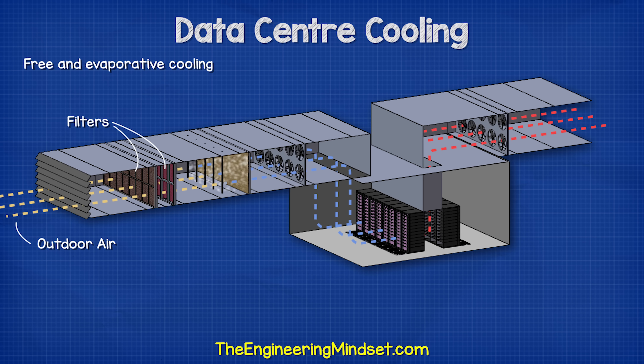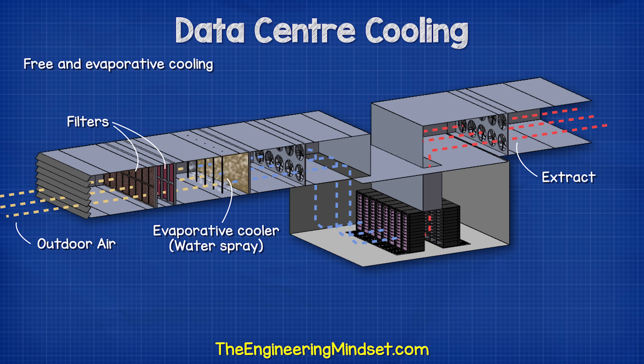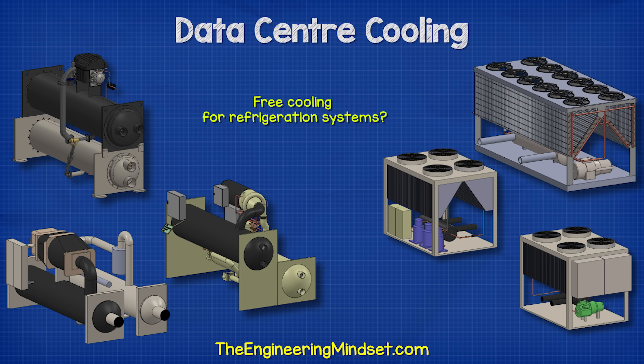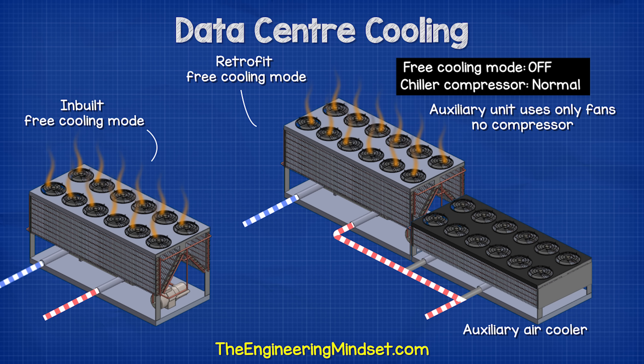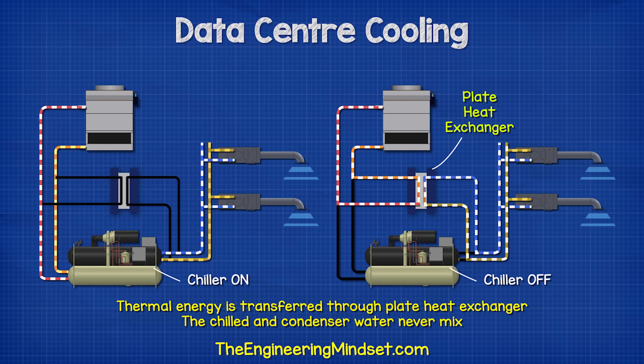Newer data centers built in cooler climates do not use refrigerants — they instead use free and evaporative cooling. In this design, outdoor air is sucked in through some filters, evaporative coolers spray water into the airstream to cool and humidify it, and the air flows directly into the server room with the hot exhaust air being separated and extracted back out to the atmosphere. Data centers with refrigeration systems can also make use of free cooling when the outdoor air is cool enough. For example, an auxiliary air-cooled condenser can be fitted which uses fans to remove as much thermal energy as possible from the condenser water before it reaches the chiller. Other designs allow the chiller to be bypassed altogether, with the chilled water exchanging thermal energy to the condenser water via a plate heat exchanger — but this only works when the outdoor air is cool enough.